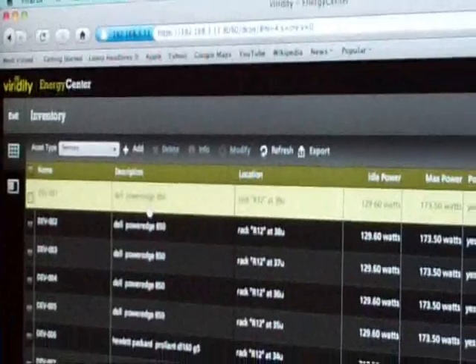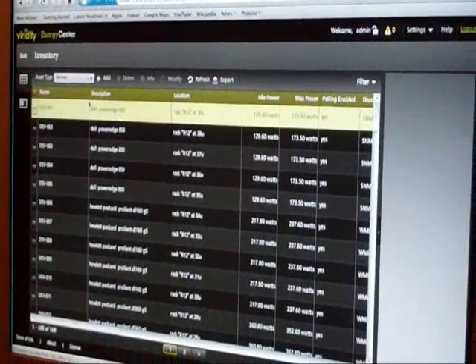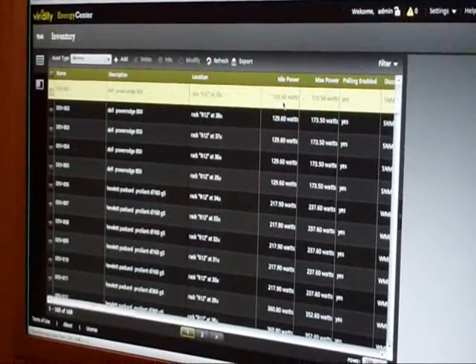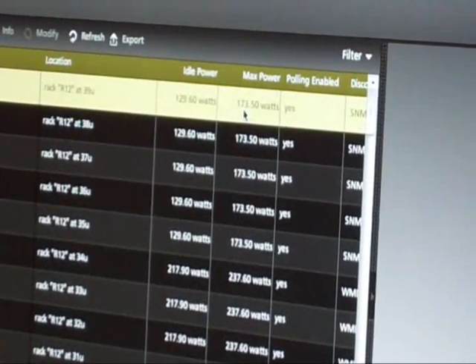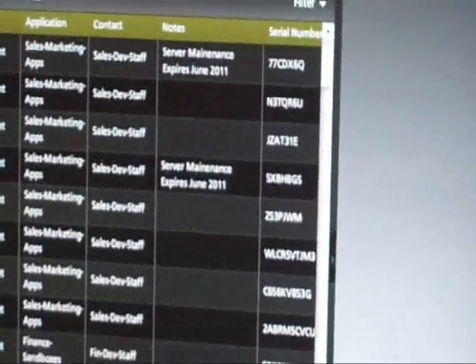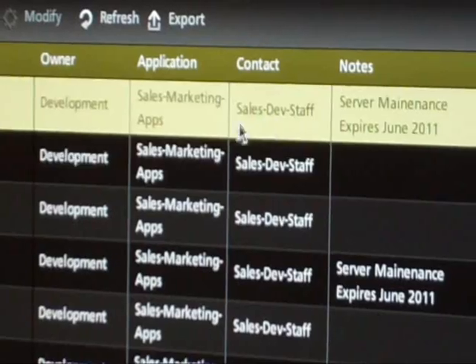Jumping to the analyze view — once discovery finds all the equipment using standard protocols, you can drill down and see the actual equipment discovered. It gives you a lot of information: what the server is, its idle and max power. Here's a server running at about 130 watts idle and 173 watts max — it's an older server so it doesn't have quite the spread of newer ones. You can also see what applications are running on it, who owns it, who the contact is. All reports can be filtered, so you can say: tell me about power consumption on the Exchange servers, tell me about power consumption in this division or this group.